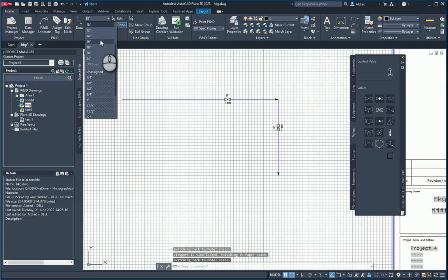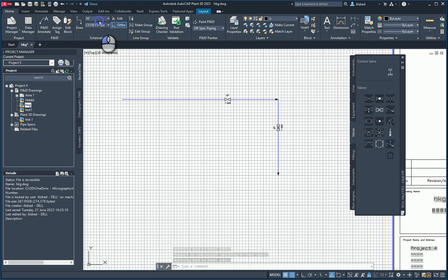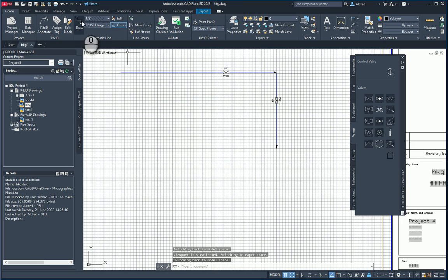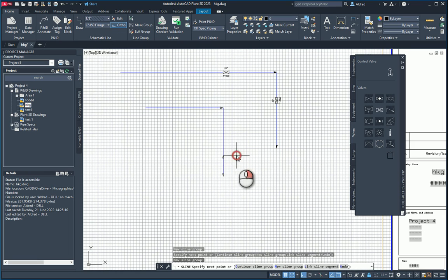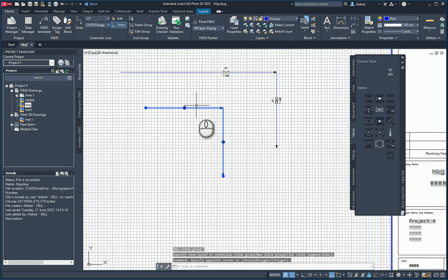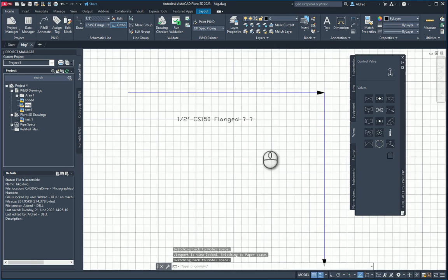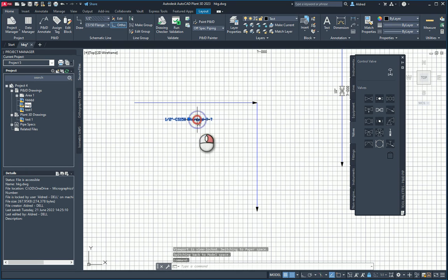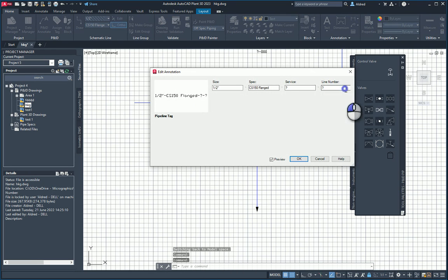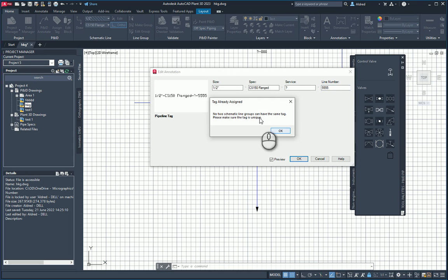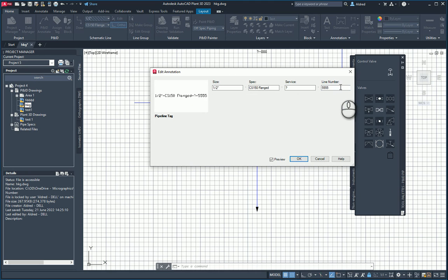Let's do an off-spec size — that half-inch spec — and see what happens when I try to bring that in. It sort of allows me to draw the P&ID, it's just that it's going to be out of spec, or nothing's going to match up when I try to bring it into my 3D. Let me put in a pipeline — 5555 — to more easily identify this.